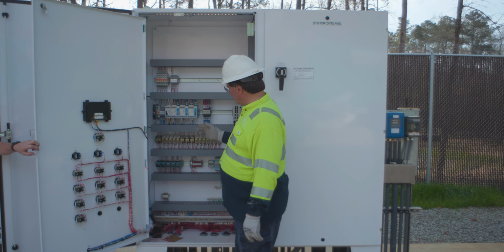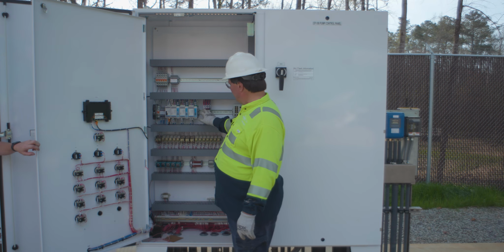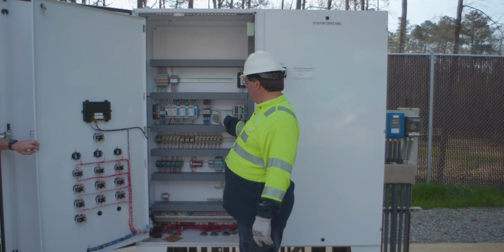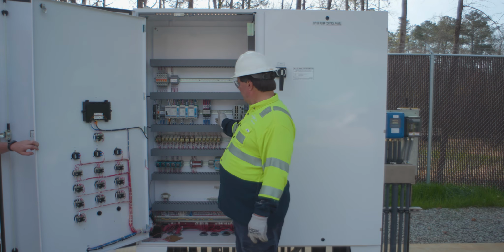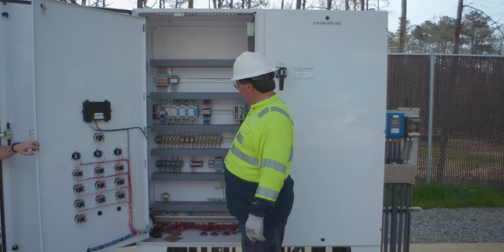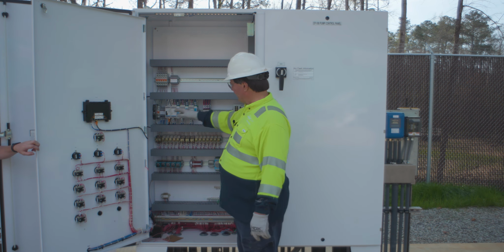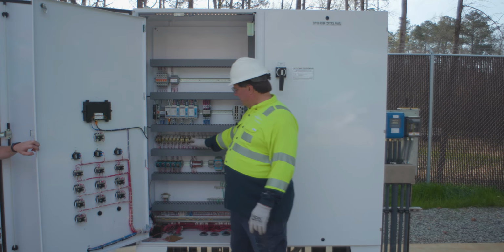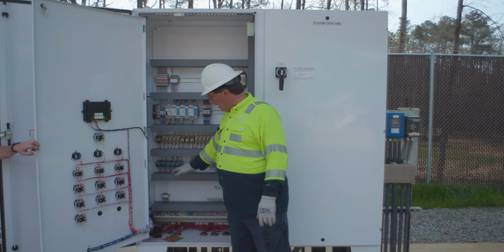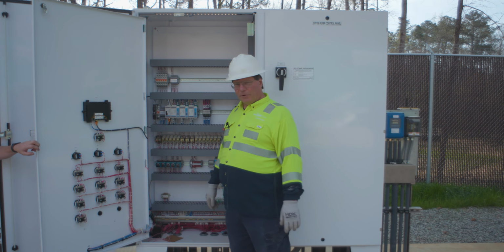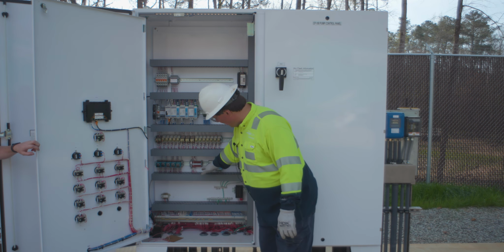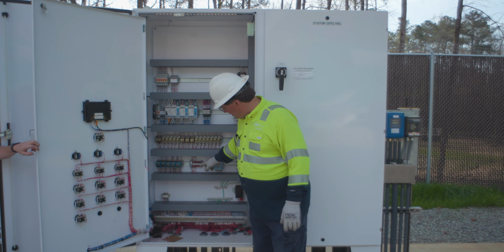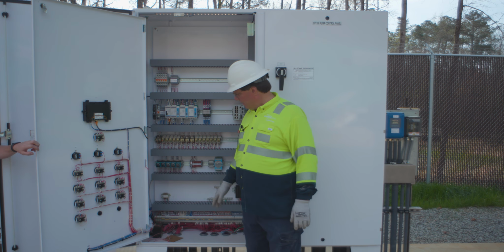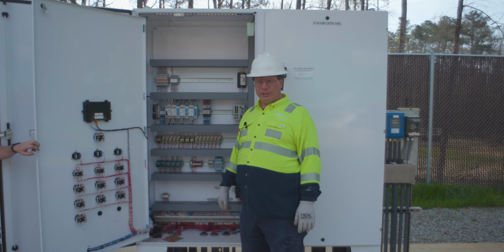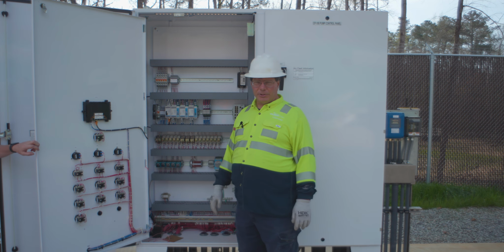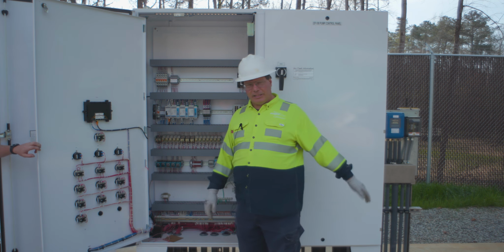Here's some more fuses, both for 120 and actually these are relays, I'm sorry. These are single pole relays for various conditions coming off of the base unit and the motor protection relays. Then we have separate relays for various control functions, time delays for starting the pump and for faults. And then we have what we just added, which is in the newest set of drawings. This is your fan control circuit. It has the fuse going out to the fan switch, and then the connections for the 120 volt control for the motor contactors we looked at there.